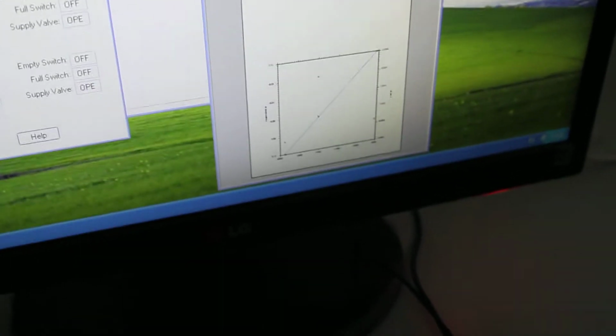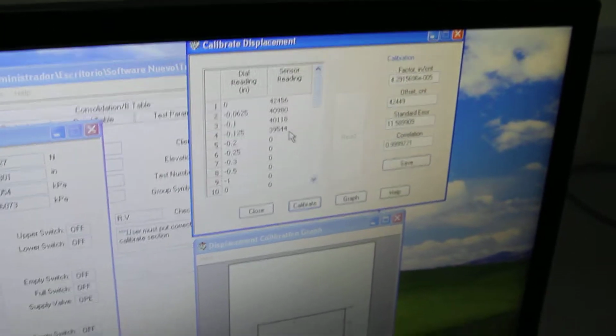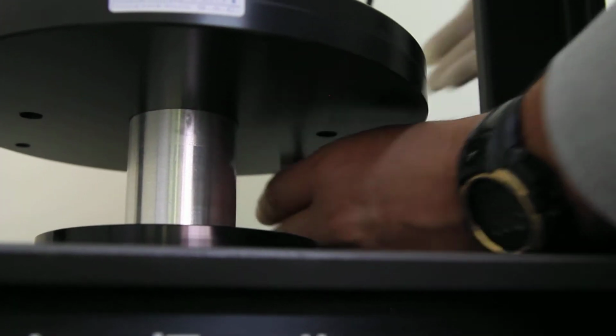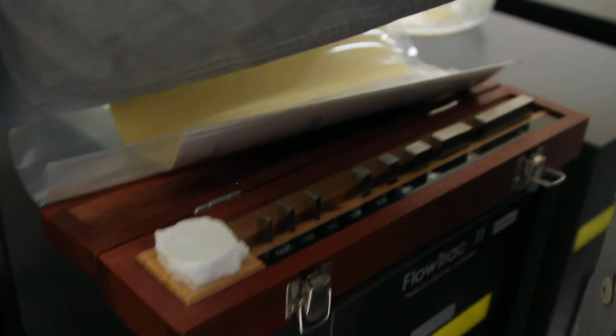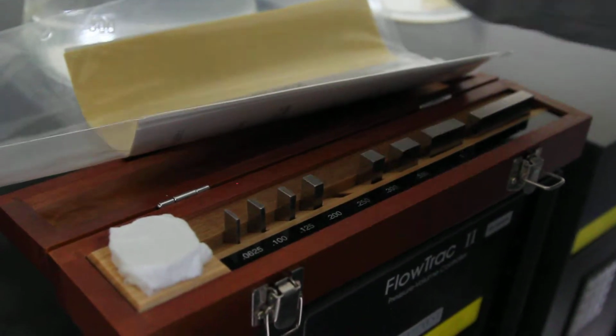I have 3 points. Then again, I'm going to repeat the process. I'm going to remove my third point and put the next one, which is 0.125, underneath, and go back to the software to the same line and do read and calibrate so I can check what's going on. Again, I will remove my third point and put the next one. So my calibration is taking place. I am already on the 4th point. So my next one.